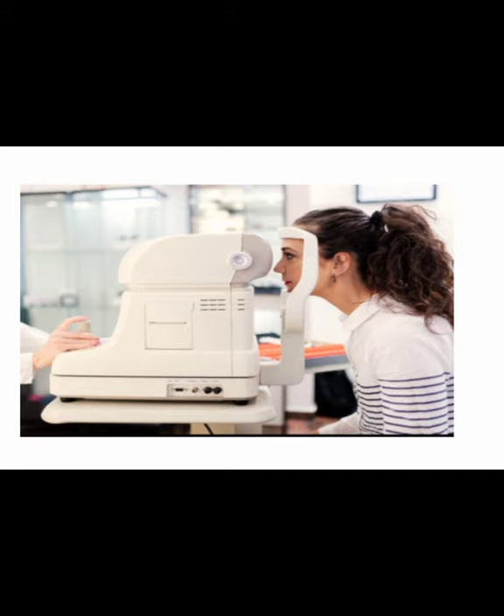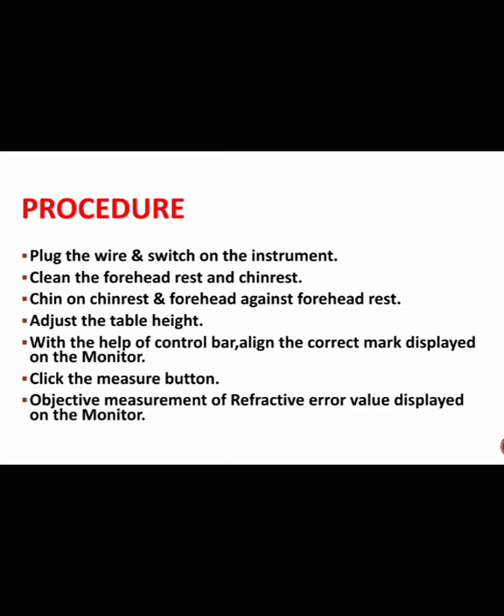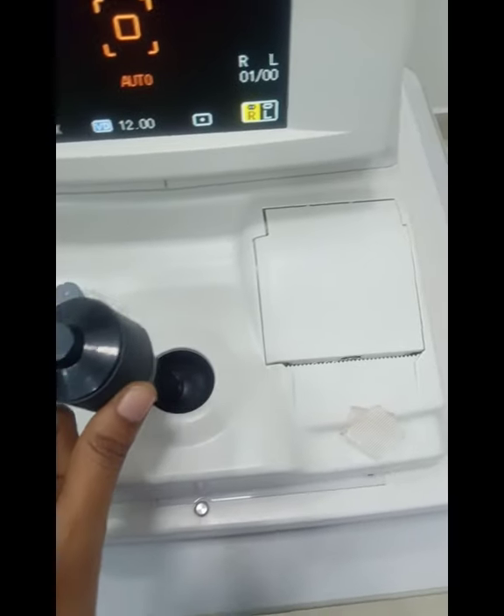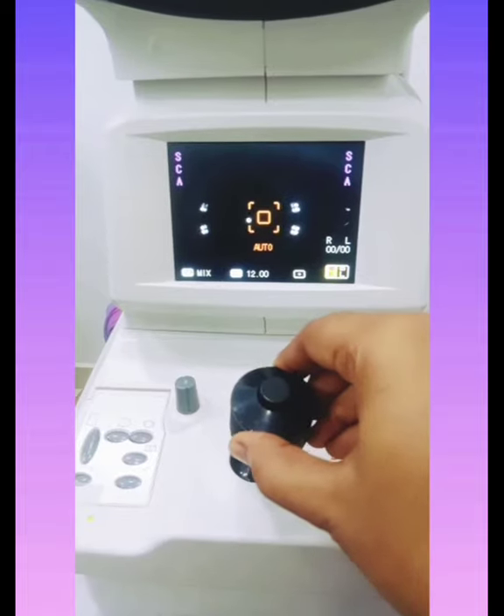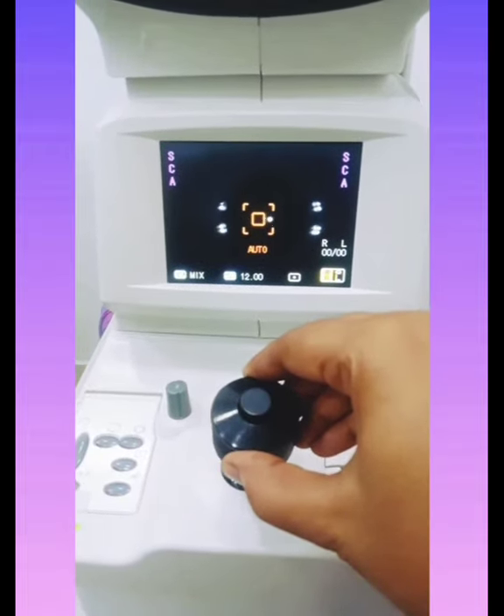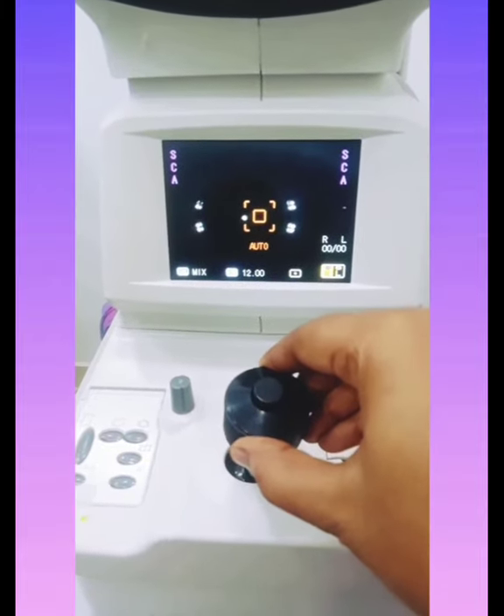If the patient is not aligned properly due to his face height, we need to adjust it by using the chin rest knob. By using the control bar we need to move the instrument according to the eye we are going to examine — either left eye or right eye. By moving the control bar left and right we can move the instrument accordingly. If we rotate the control bar upwards and downwards it moves upwards and downwards accordingly.